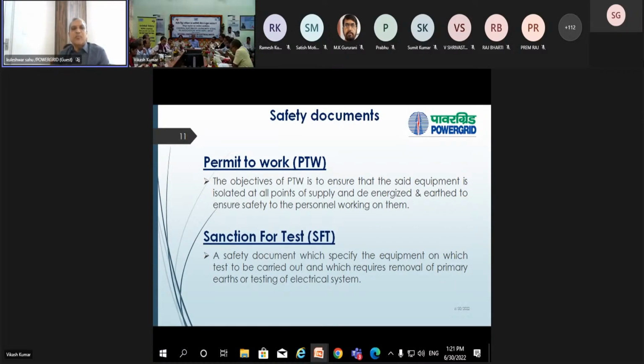So there is a definition of permit to work and sanction for test. I will describe. Permit to work is issued where we have to permanently earth both the sides. Like we are working on the transmission line for change of insulator. So at both the substations we have to close the earth switch permanently. In that case, we will go for the permit to work.